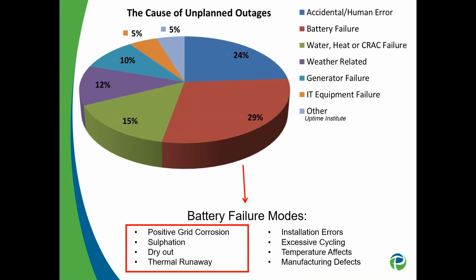Some of the battery failure modes you can see on the bottom are positive grid corrosion, sulfation, dryout, and thermal runaway. The next modes are installation errors, excessive cycling, temperature effects, and manufacturing defects. Those are the other ones that can cause these problems. You will see the installation errors and the manufacturing defects at an infant stage, probably right away when you're doing your battery system commissioning. Excessive cycling and temperature come over time.